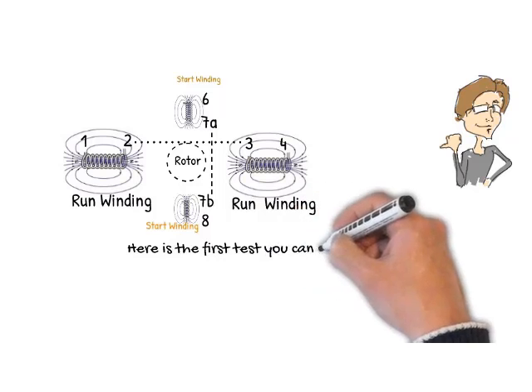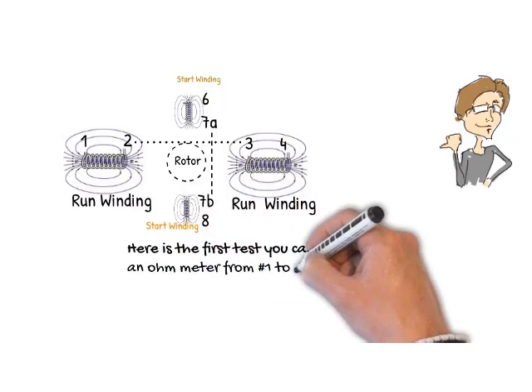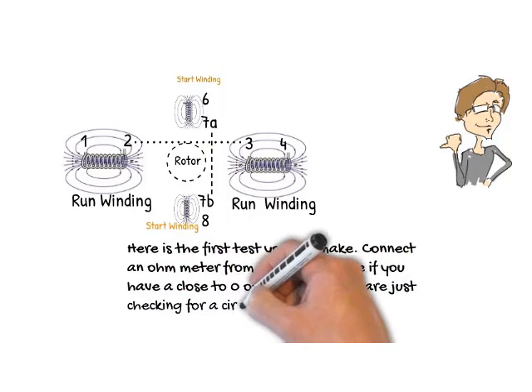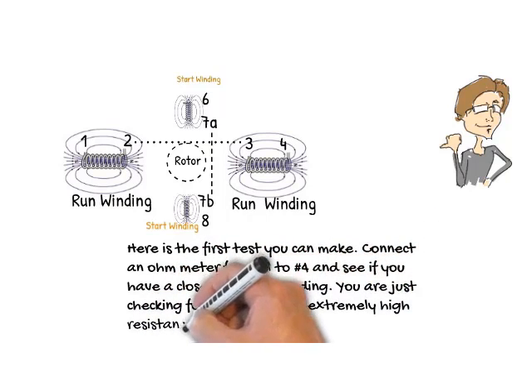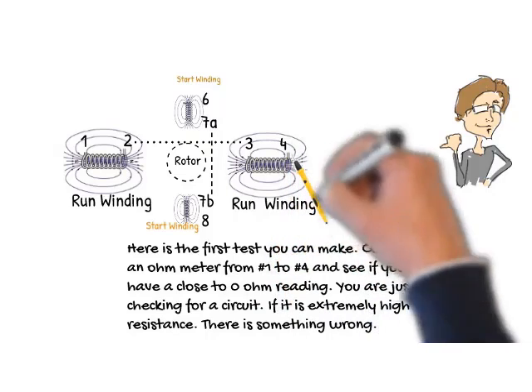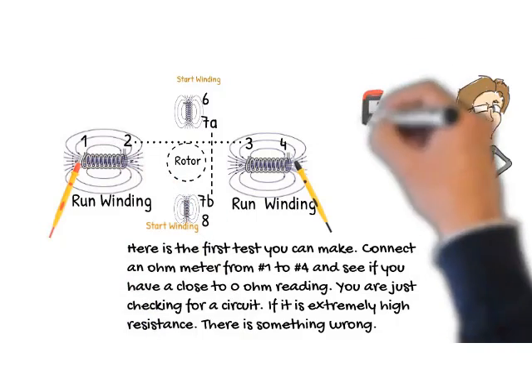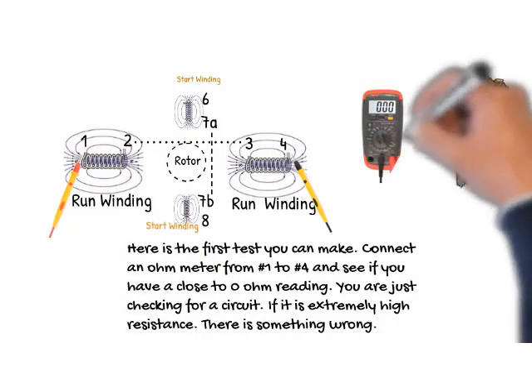Here is the first test you can make. Connect an ohmmeter from number one to number four and see if you have a close to zero ohm reading. If it is extremely high resistance or infinite, there is something wrong in the motor.